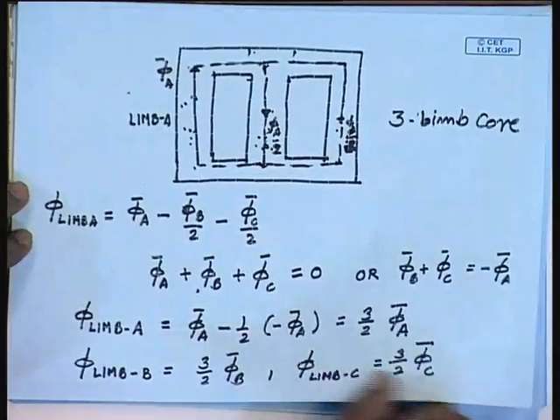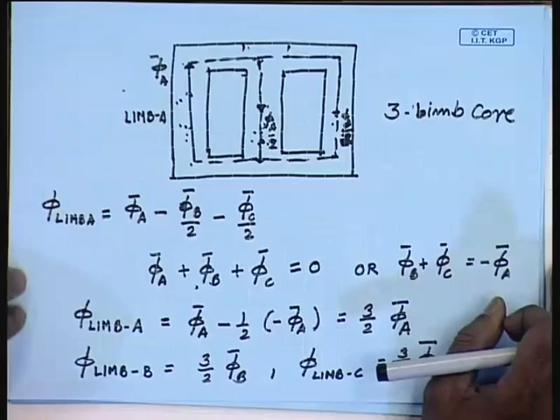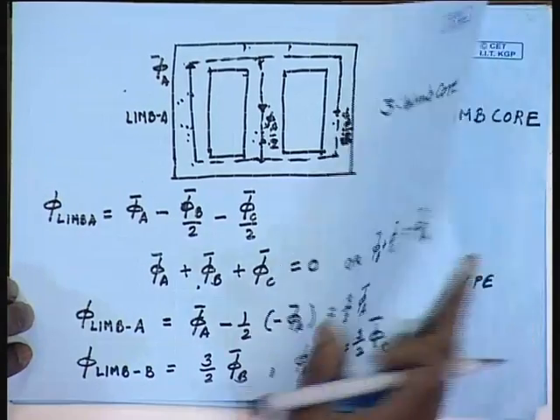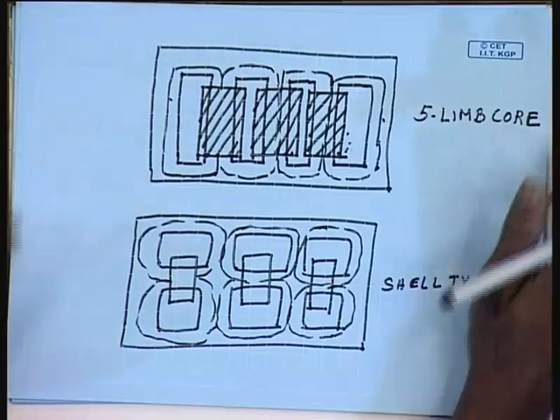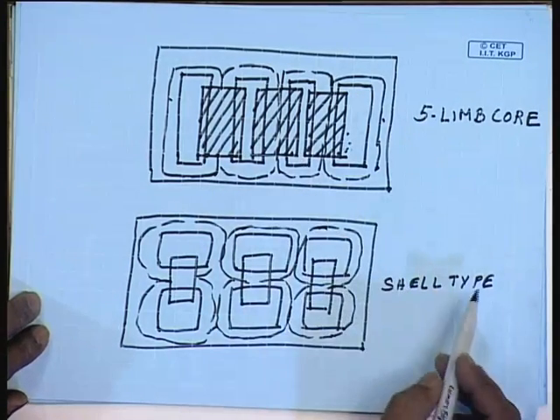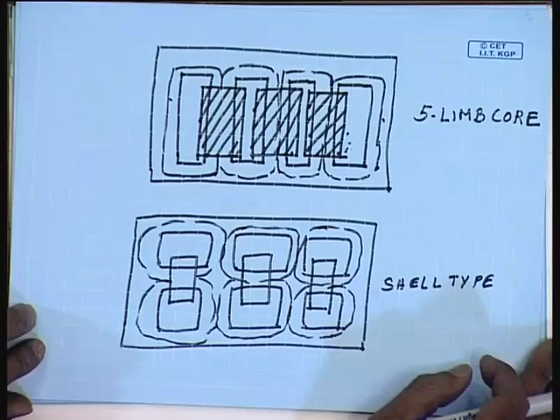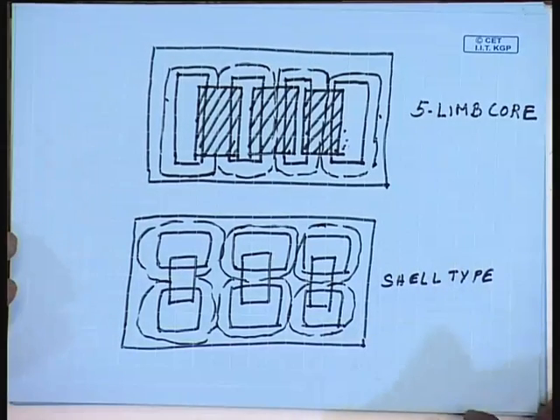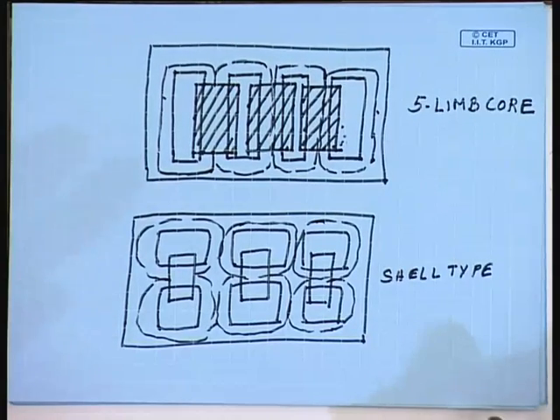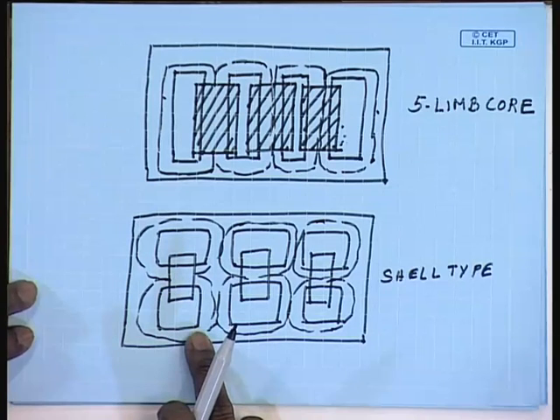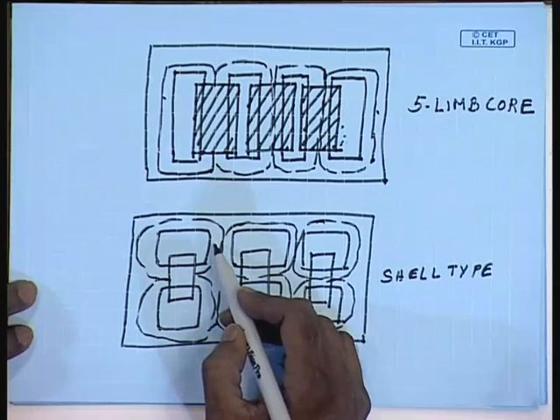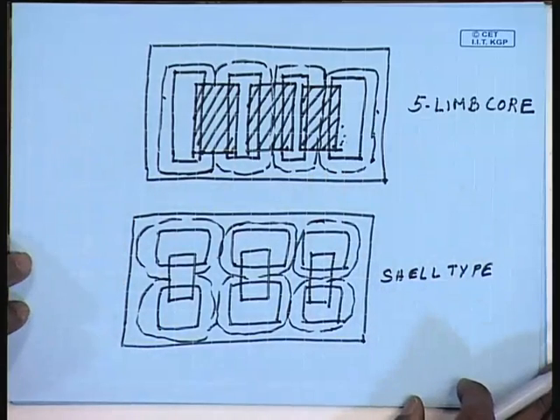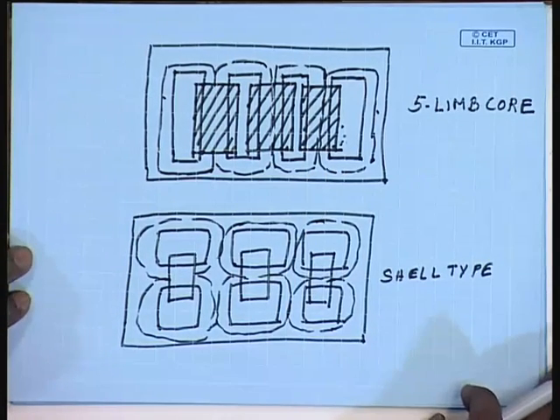So, although 3 phase transformers are most commonly found with a 3 limb core, some very large transformers are also built with a 5 limb core or a shell type core, where the magnetic circuits of the phases are either symmetric or independent. But as you can see, at least for the shell type core, this is little more than 3 single phase transformers connected together. So, this does not offer the advantages of the 3 limb core, and it is seldom used.